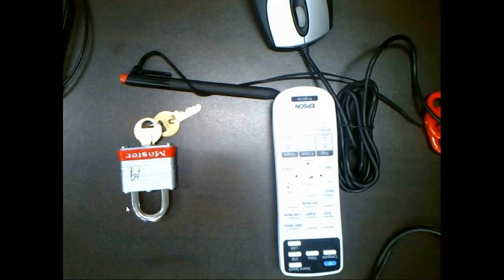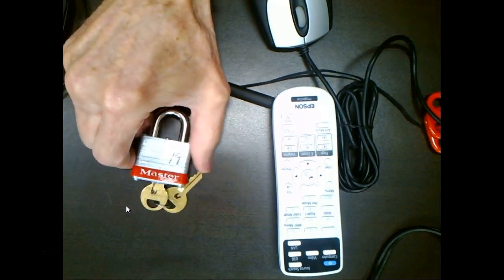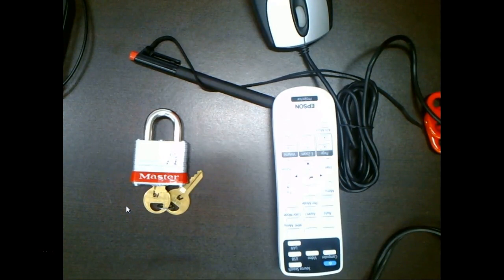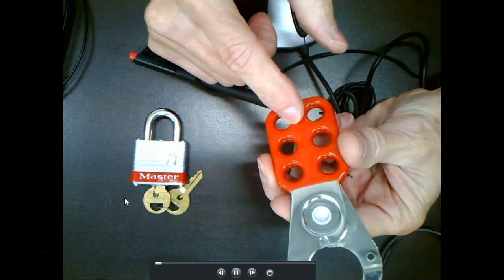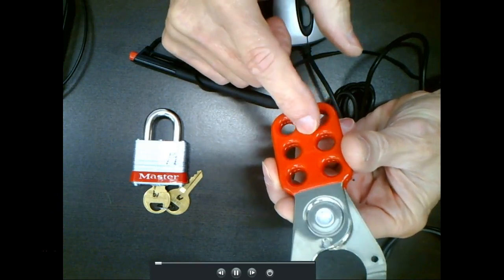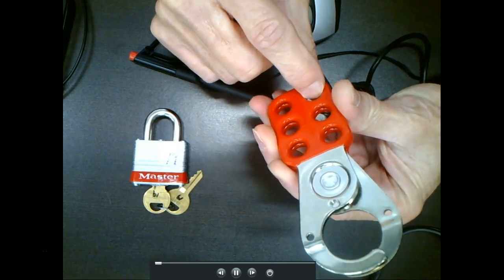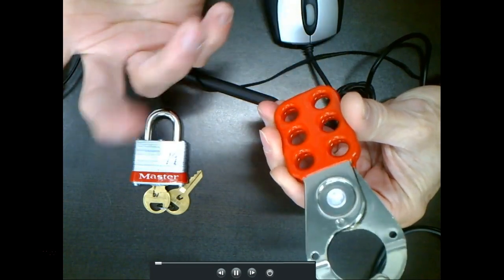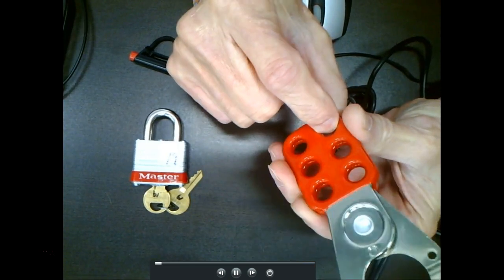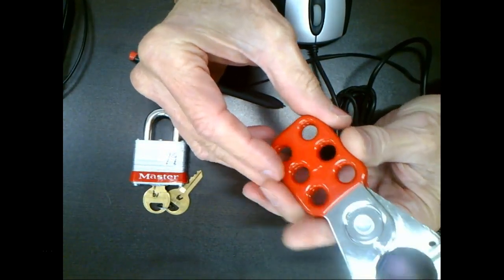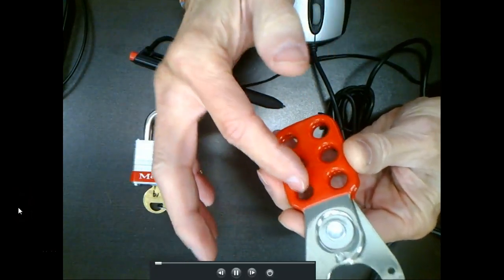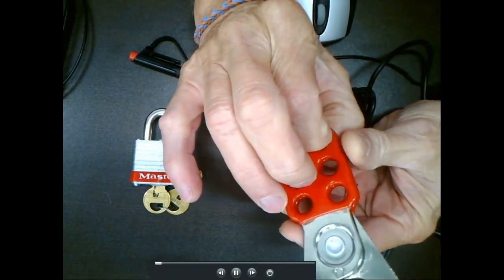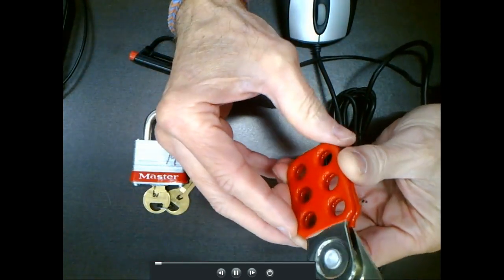Now, if you saw over there on the robot, it only had 1 lock. Well, if you got 5 people working on there, then 5 people should each put one - every person working on the system, you don't depend on other people's lock. Everybody working on the system needs to put a lock. You come over here and you never use all 6 of these - you use 5 of them and leave 1 blank. Why? In case somebody else comes along and you've used all the locks. So we could come in and put another extender down here and get 5 more. That makes sense? So you should never use these 6. If you need another one, you get another extender and clamp it up here. That way you're always ready if somebody else needs to come up and work on it too.